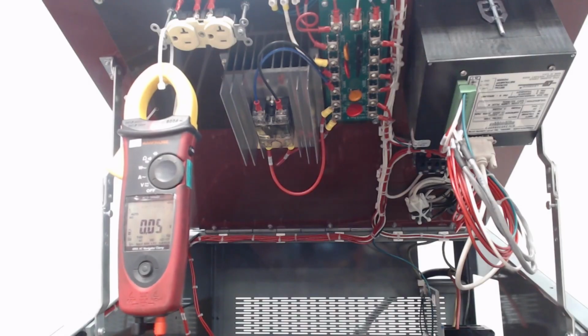You can account for that incoming voltage, and that'll be based off the power from your facility because it's not going to be the same day to day. So your 460 may be coming in at 420, maybe coming in at 480. If it's beyond the 10-15% tolerance, then you may need to look into fixing that. The unit will work, but you do need those tolerances to make sure everything works to the best of its ability. And it will certainly help if you're running into issues, especially with fuse blowing, to have everything properly aligned.